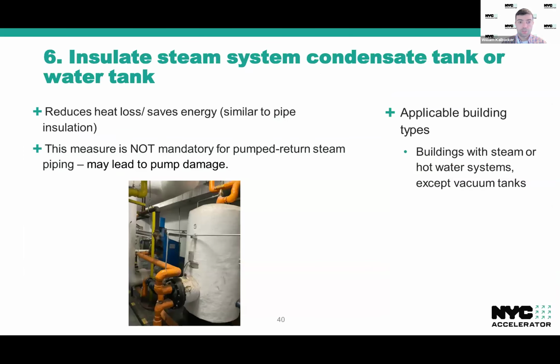Measure number 6 is to insulate steam system condensate tank or water tank. So basically here, if you have a large metal vessel filled with a hot fluid, it's going to try to radiate that heat out, very similar to how an uninsulated pipe might. And your central equipment is going to have to heat that back up if there's losses. So if you insulate your tank, you're going to prevent those losses and save energy. That's the general idea here.